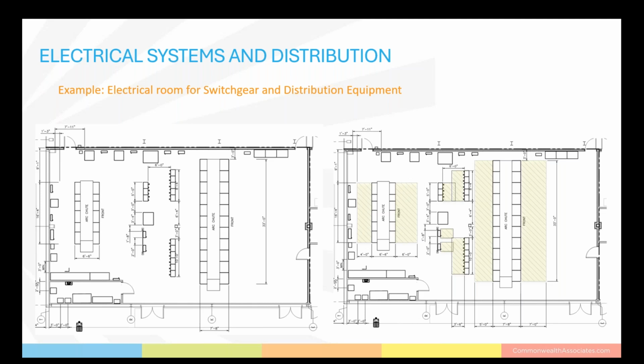The layout on the left is shown with the basic equipment only, and it looks fairly open, but when those clearances and maintenance spaces are shown as in the right view, it tightens up the available free space in the room. This layout allows for access to both the front and rear of the equipment. Should the switchgear require only front access, the rear space could be reduced to roughly 4 to 6 inches just to keep it away from the wall.